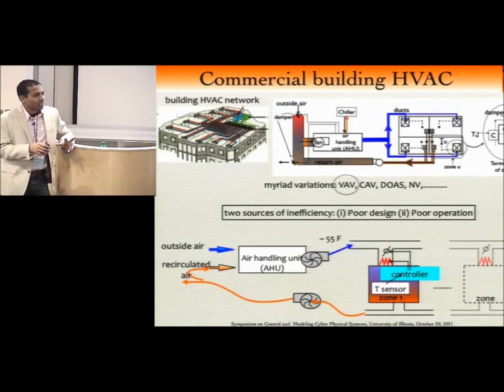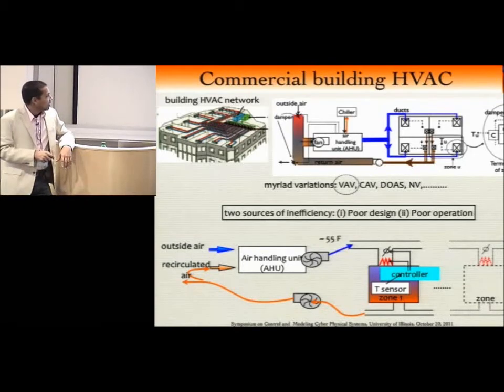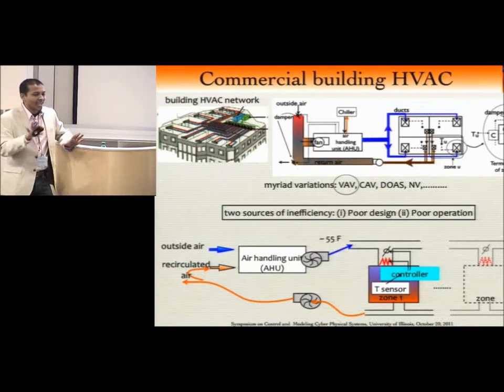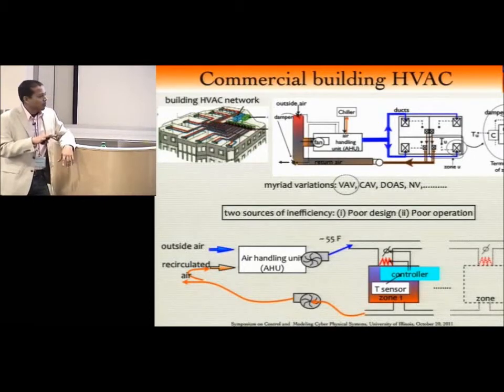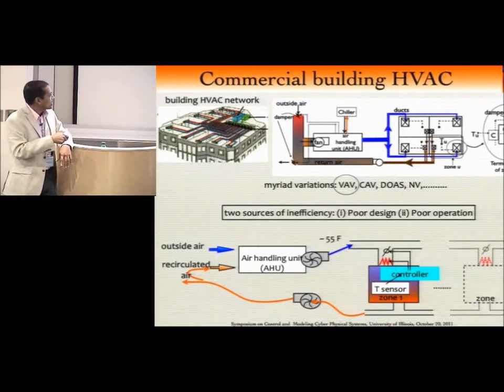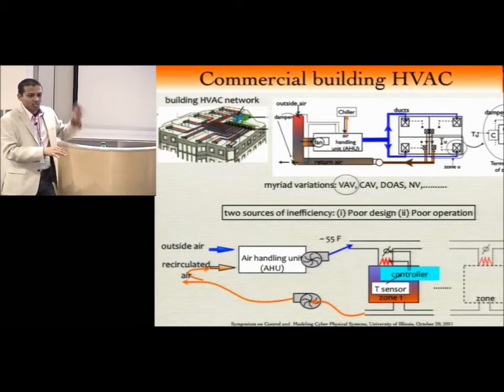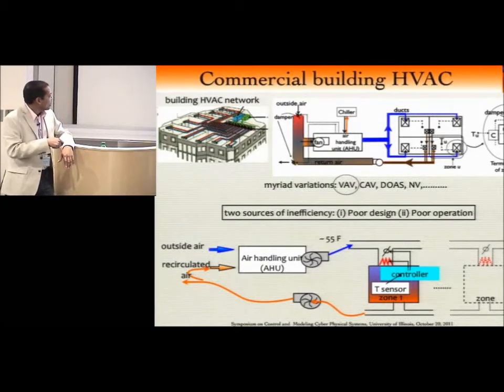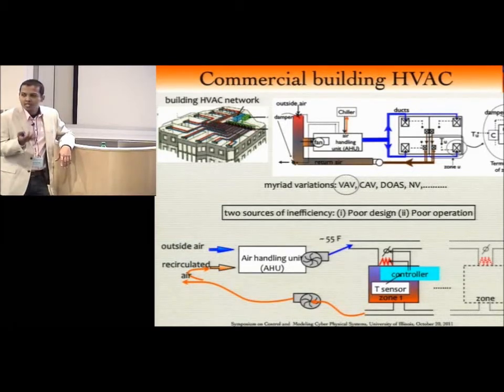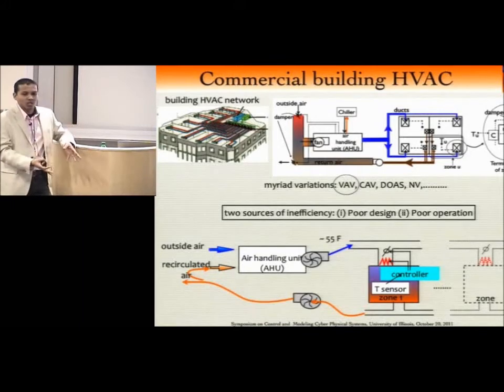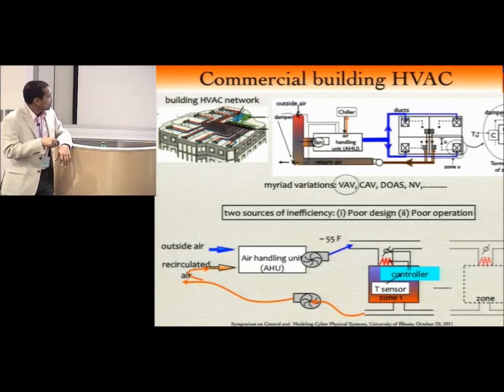So what happens is a local controller. There's one temperature sensor. In that case, it's over there, and that's supposed to be representative of the whole temperature in this room. And then there's a local controller that looks at the temperature, and then there's a desired set point of temperature. And it compares the two, and based on that, it does two things. There are only two inputs it can change. One is the flow rate of air coming into the room. The other is the temperature. Although the air is supplied at a certain temperature to the room, which is usually pretty cold because you cool it down really drastically, usually around 55 degrees Fahrenheit, but that varies from climate zone to climate zone. And at the supply point, the controller can actually reheat the air, because if it determines that if I supply cold air at 55 degrees Fahrenheit, the temperature is going to go down too much, then it can reheat the air. So there are two things it can do at that point.